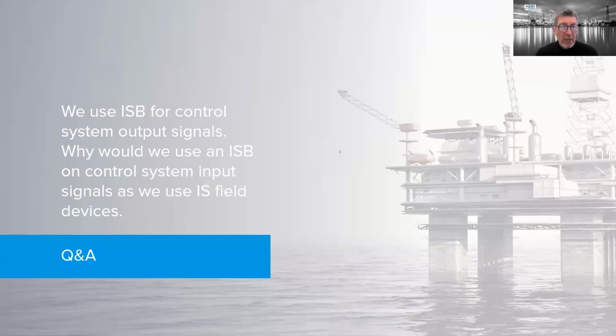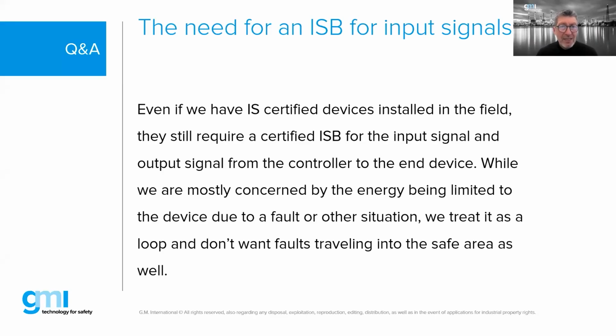When we use an IS barrier for control system output signal, why would we use an ISB on control system input signal as well as on the IS field device? This must be the same question we already answered. It's actually very similar. Basically, you need a barrier regardless. Even if we have IS certified devices installed in the field, they still require a certified ISB for the input signal and output signal at the controller end.